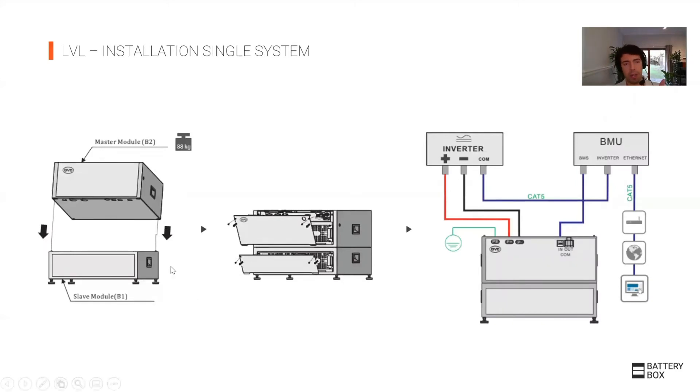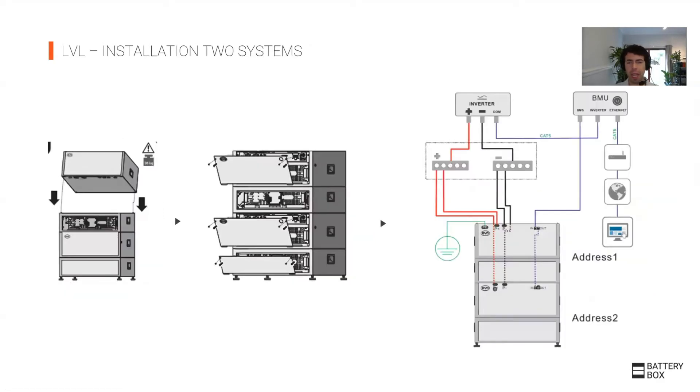As mentioned, the complete LVL unit comes in one box, but the modules can be quite heavy, which is why they are separated into two halves so two or three people can handle the weight. When you stack one on top of each other, there is a pass-through cable and a pass-through hole in the bottom of the LVL, allowing cables to run neatly through the inside of the batteries.